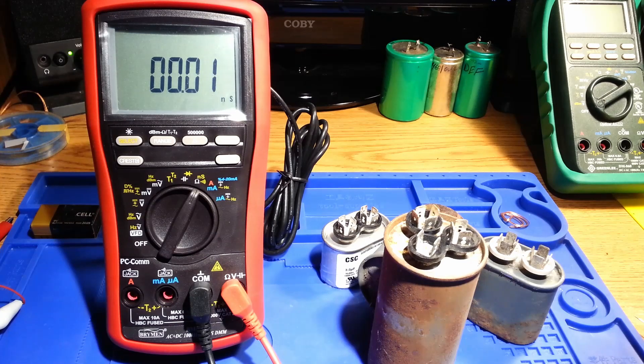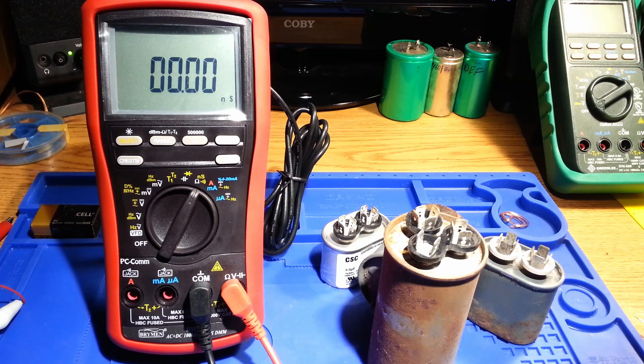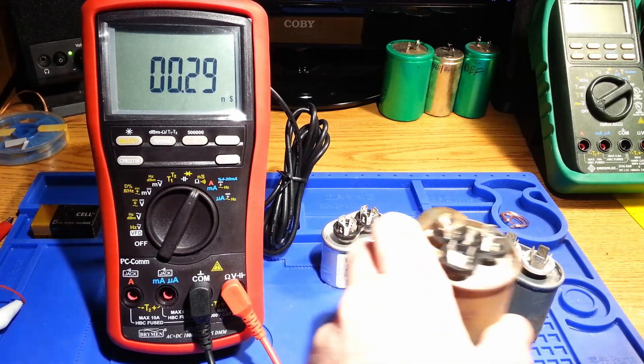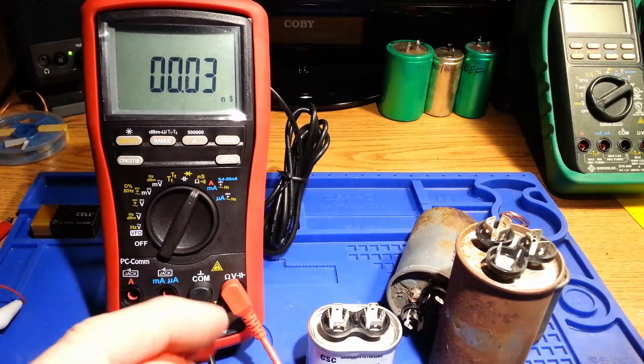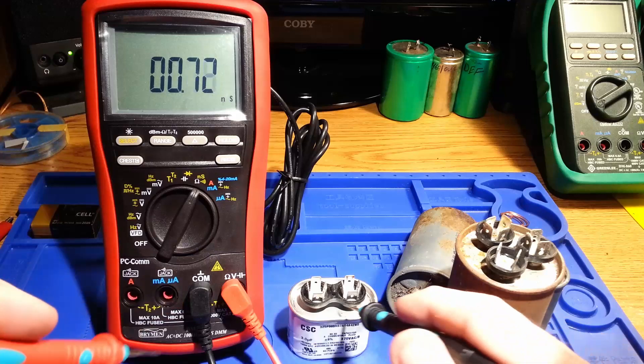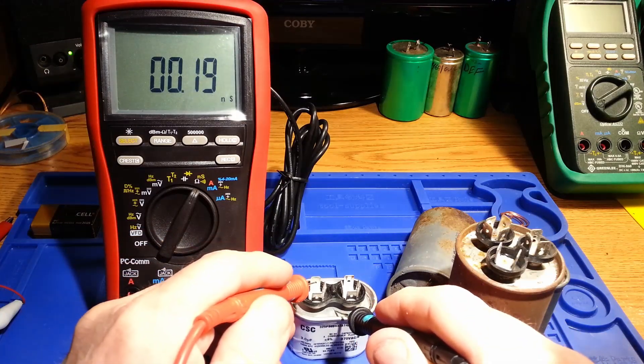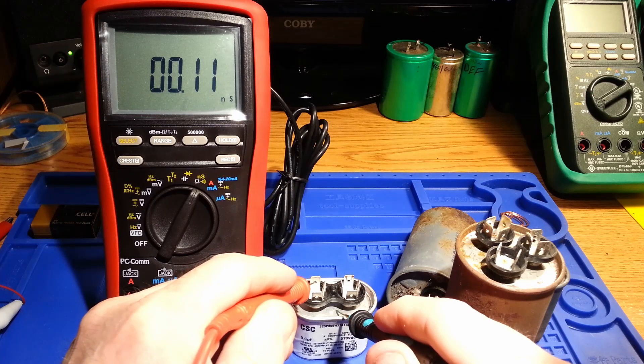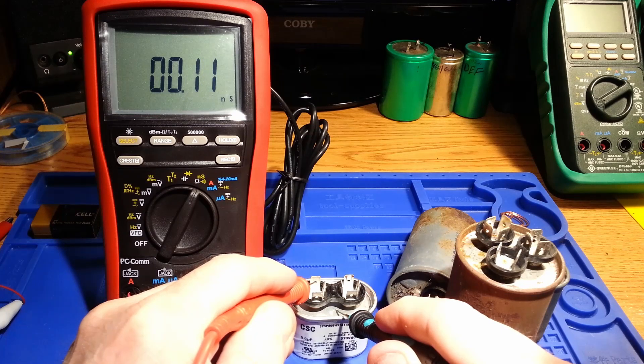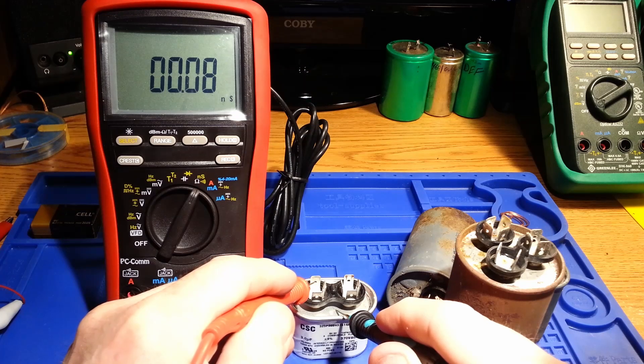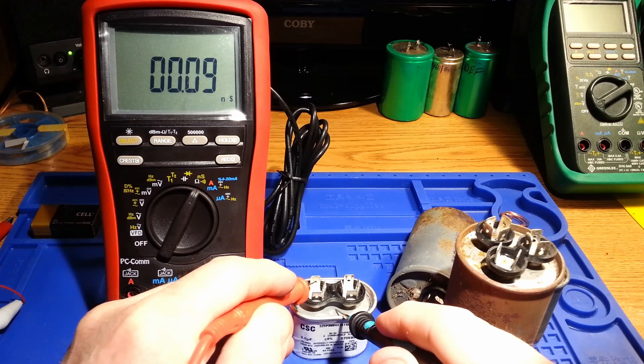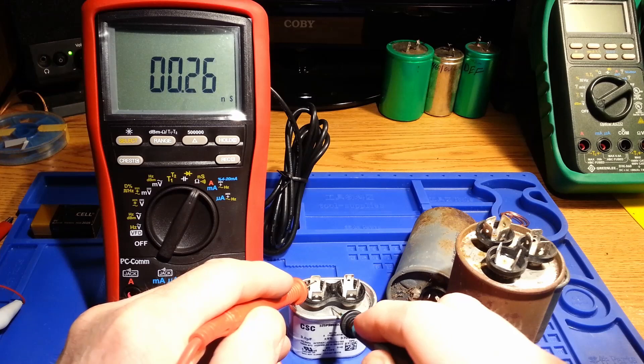Now a 0.01 on this is 0.01 nano siemens, and conductance is the inverse of resistance mathematically. And an indication of 0.01 would be a hundred gigaohm resistance. And in this case, I am going to go between the case of the capacitor, the new capacitor, and one of the leads.